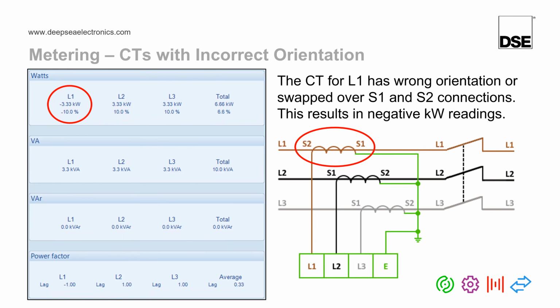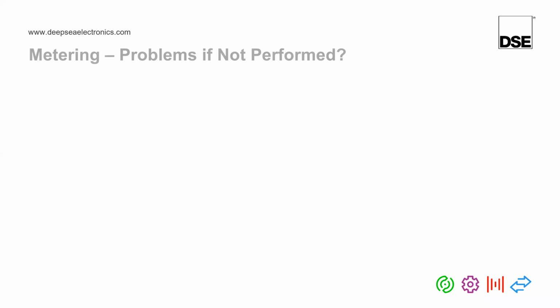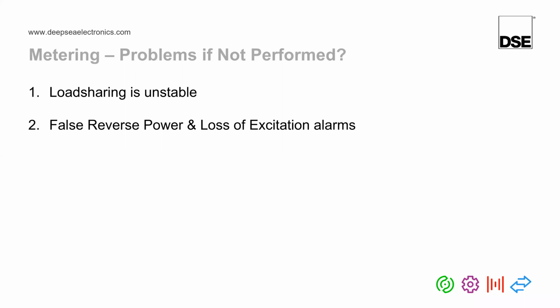So it's extremely important that we check the CTs, because if we do not, it is very likely that you'll end up having bad load sharing and also spurious alarms for faults that do not actually exist. Before we go on to the third step, I'm just going to go back to Dave to go over the questions that we've been asked.